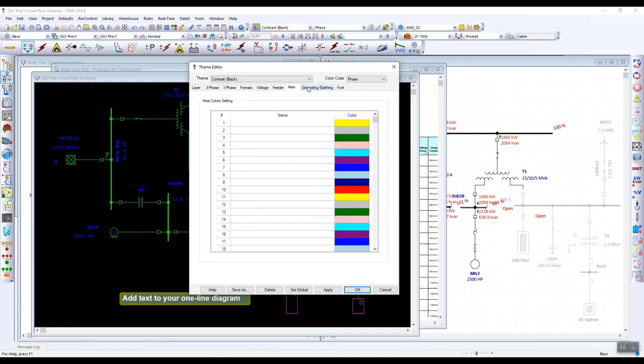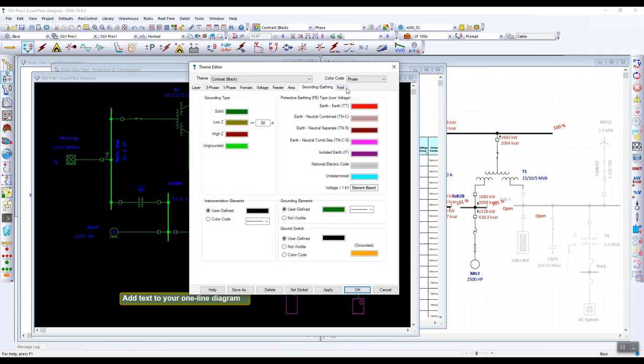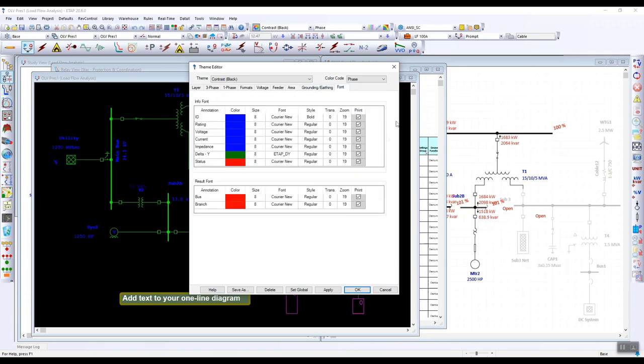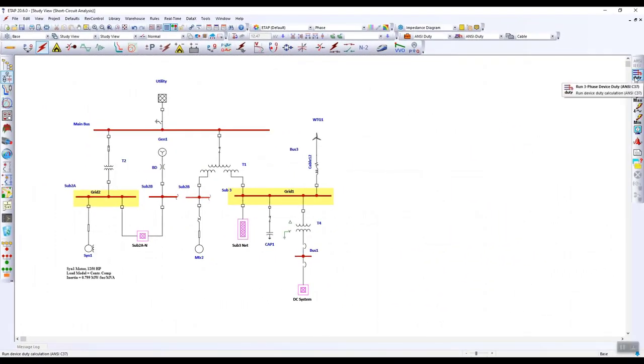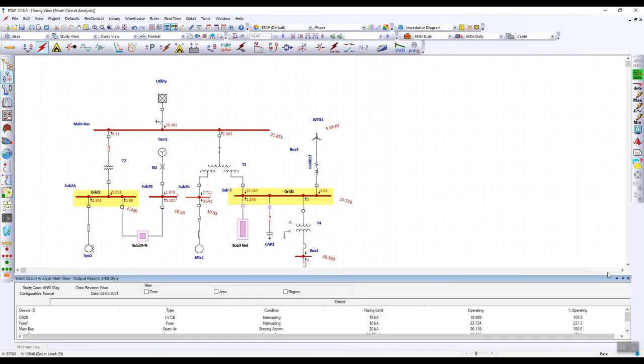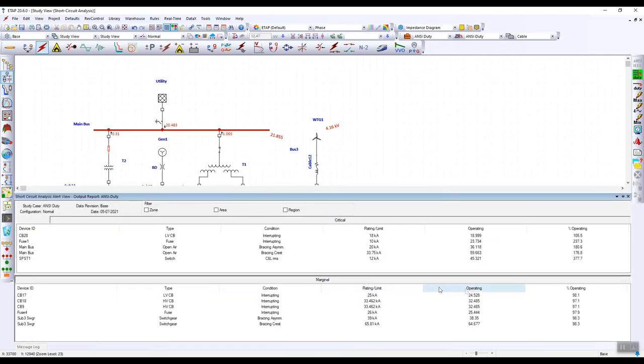We can change the color for grounding connection lines, for grounding and earthing, and last, you can change the font for your results and input annotations. In short circuit, we can run a three-phase and single-phase device duty study, half cycle, 1.5 to 4, and 30 cycle, for line to ground, line to line, line to line to ground, and three-phase faults. Once we run our device duty calculation, we can check our alert view and see our marginal and critical errors based on the percent thresholds that we set in the study case for short circuit.